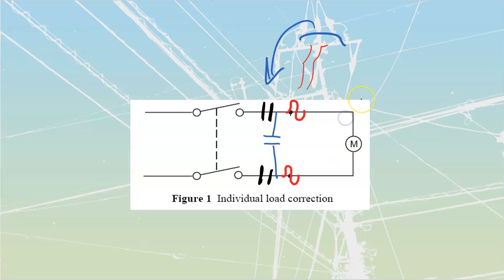If I apply it that way, it gets the full motor current, the full VA going through it, which means I don't need to downsize these ones. It's a little tricky because in a lot of cases the contactor and overload are built together. But if you have the option of an individual large load connection, and can go from an individual contactor to a standalone overload, that would be the ideal place to put it, so you can match this to that. Otherwise, you just have to do some additional mathematics.